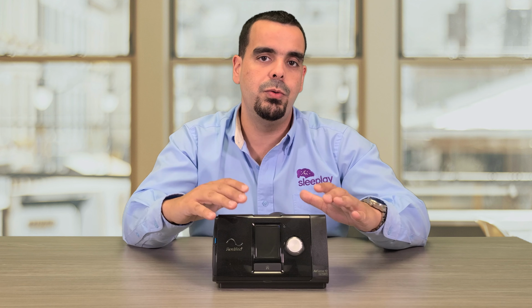Two great features about the ResMed AirSense 10 are the auto ramp feature and the auto humidity feature. The auto ramp feature lets you choose auto, and the machine will gradually increase the pressure depending on how many obstructions it's sensing. So it can go anywhere from 5 minutes to 45 minutes, but the machine will choose for you. The auto humidity setting controls the humidity based on the humidity in the environment. So it maintains a level of humidity throughout the night.